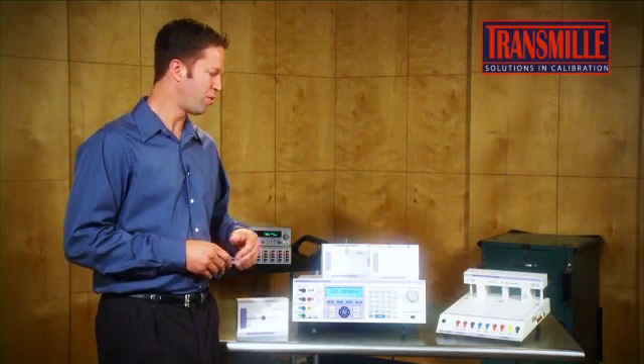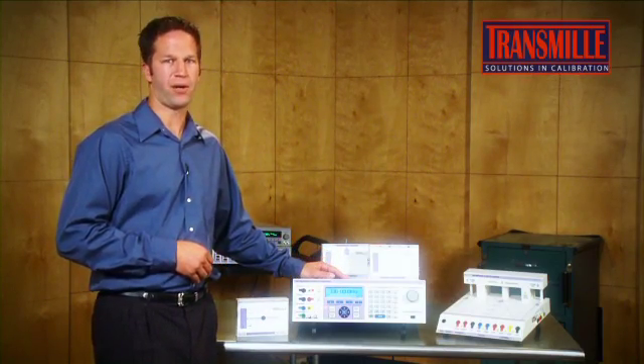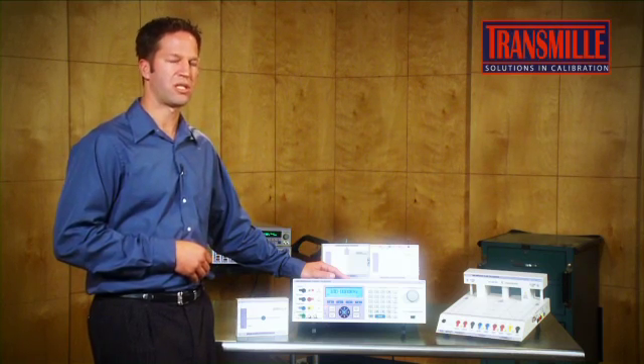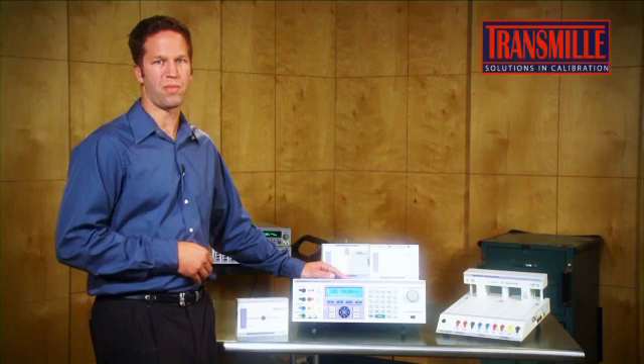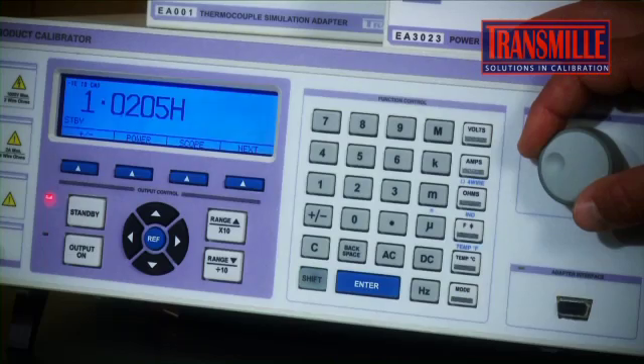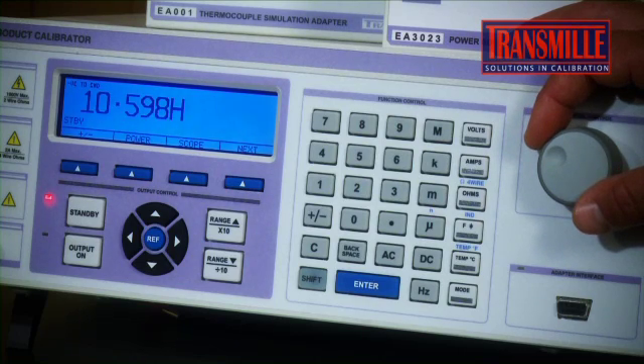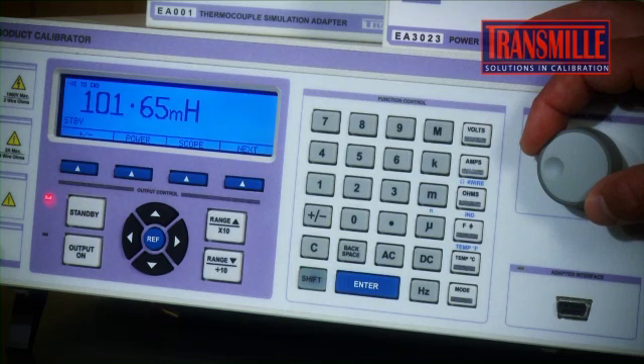Similarly, in frequency, the Transmille calibrators offer up to 10 megahertz, while competitive units offer only 2 megahertz, which is not enough to even calibrate some of the most basic DMMs on the market. Transmille calibrators also offer an inductance output feature, not available in competitive models, which allows you to completely calibrate RLC meters through an appropriate range.